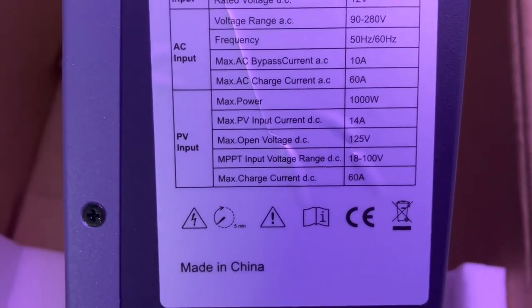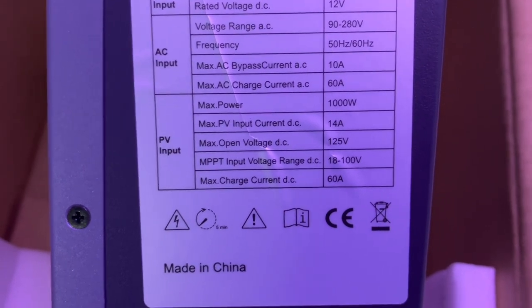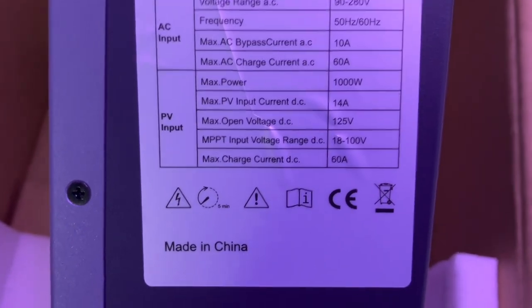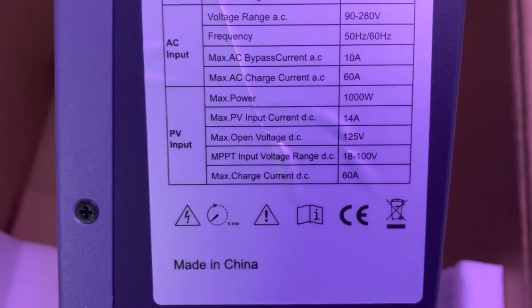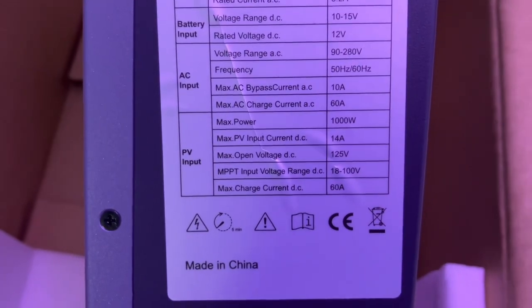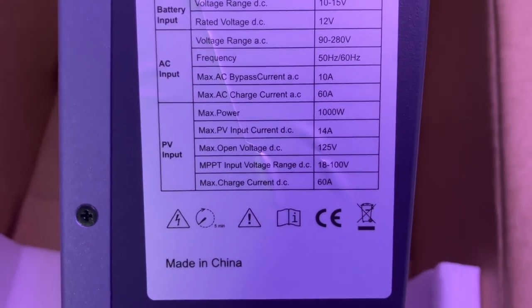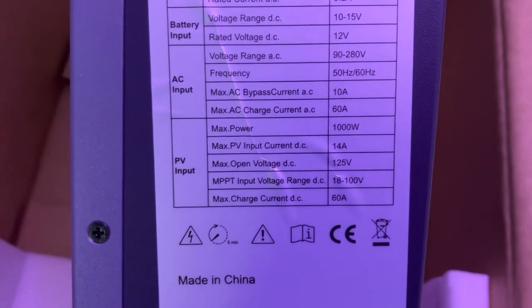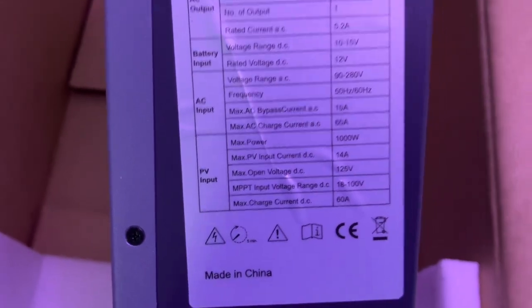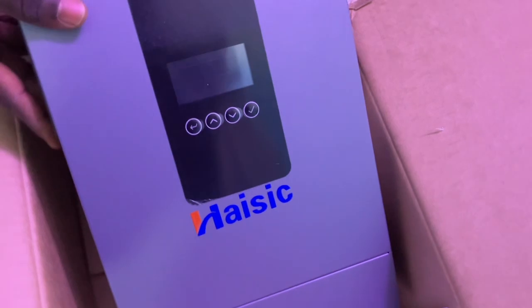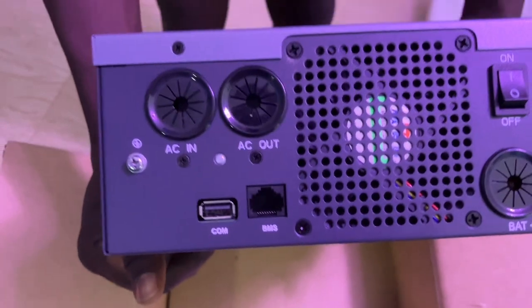That means you can use two panels of 50 volts. Okay, so the MPPT range starts from 18 volts to 100 volts. So if your panel exceeds that, the inverter might not charge, and you can charge with a current of 60 amps through the charge controller inbuilt. Okay, so this is an off-grid inverter, and it has some features that we'll look at shortly once we connect the battery. Okay, so let's look at the bottom here.